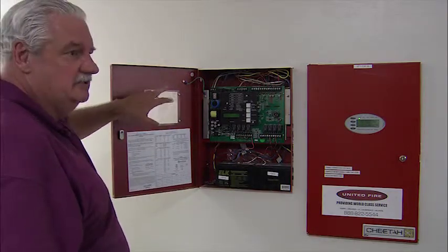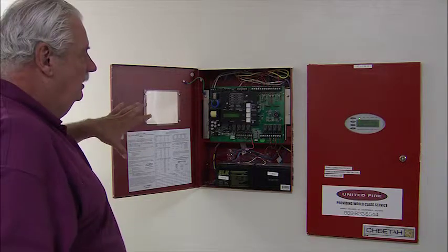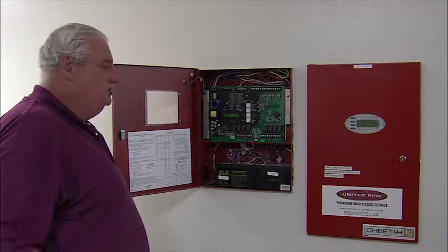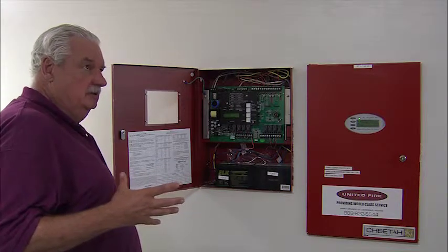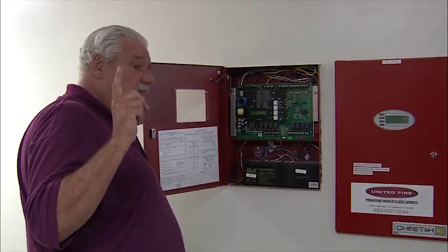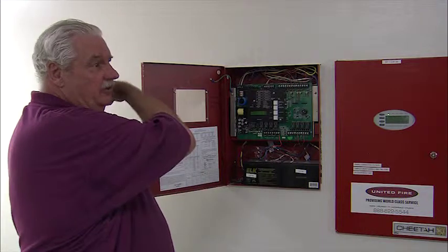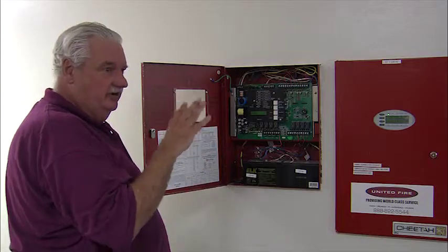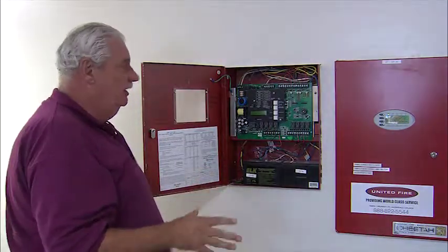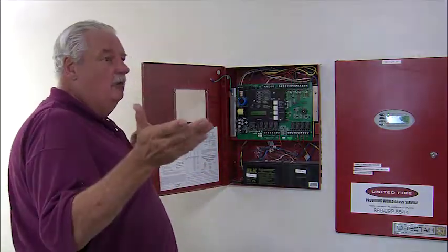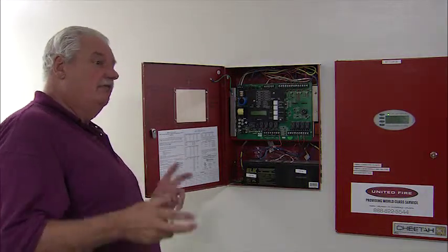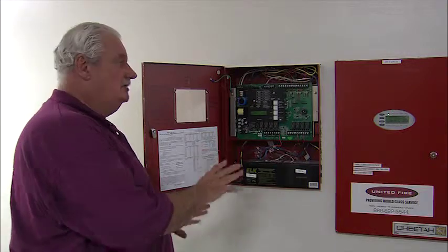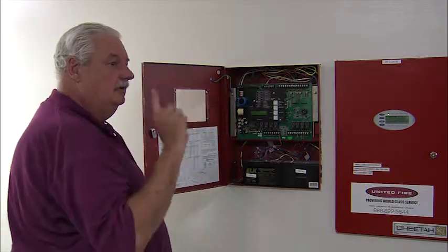There's heat detectors on these. They're fixed temperature heat detectors. The zones are also labeled, so you shouldn't have to guess. Zone 1 and 2 covers the studios, the second floor, I believe the new control room, and a stairway on the second floor. There's a zone for each one. In order for water to get into that system, you have to have 2 heat detectors go. But if 1 heat detector goes, it's going to activate an alarm on here and sound your building alarm.